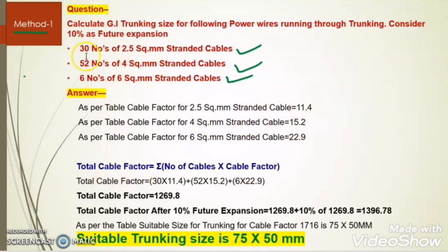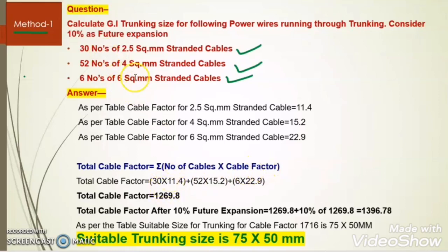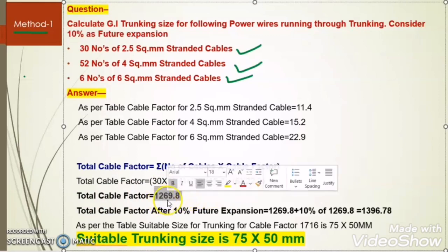The total cable factor formula is the sum of the number of cables multiplied by its cable factor. So: 30 into 11.4, plus 52 into 15.2, plus 6 into 22.9. The total cable factor is 1269.8.